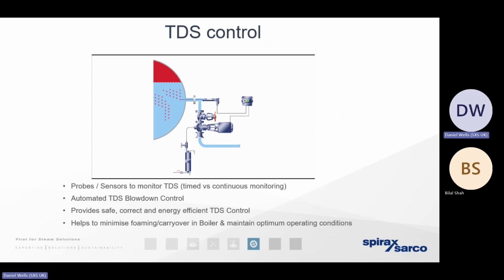Now, if we allow the TDS level to rise to a very high concentration, we're going to get a lot of foaming present that sits on the surface of the water. And as the boiler fluctuates in pressure to keep up with the demand, that foam is going to expand and it's going to be drawn out of the boiler and into the pipework. That foam is going to be very, very wet, sticky. It's going to result in a poor condition of steam. That foam is going to dry out to scale. It's going to create erosion of sensitive areas. It's going to bind itself to heat exchangers, resulting in a barrier to heat exchange. But if we're blowing down too much of that hot water to waste, we're going to have a huge financial inefficiency.